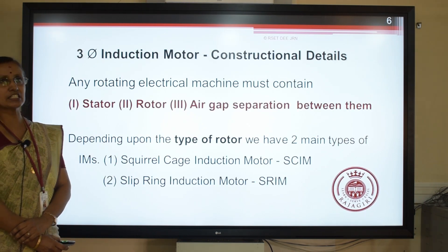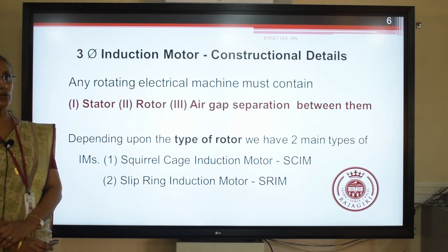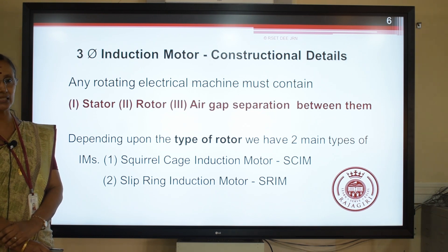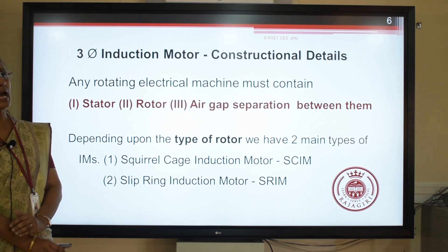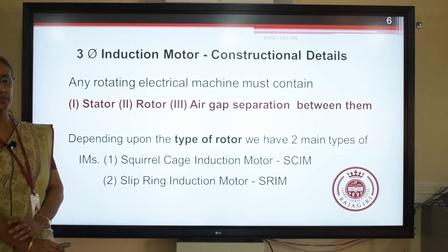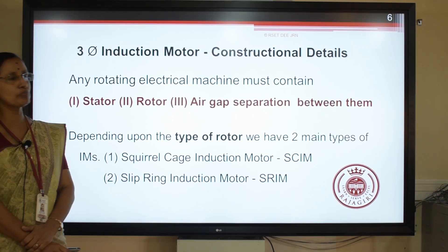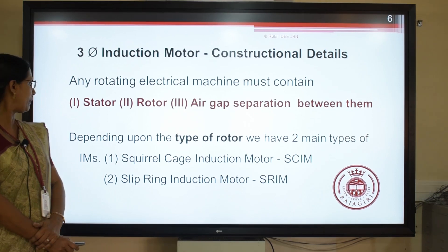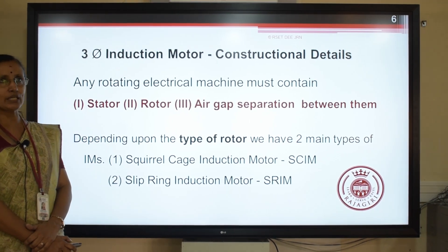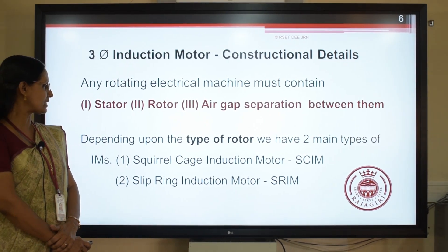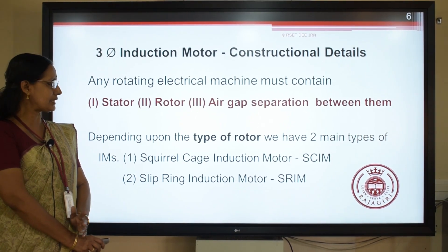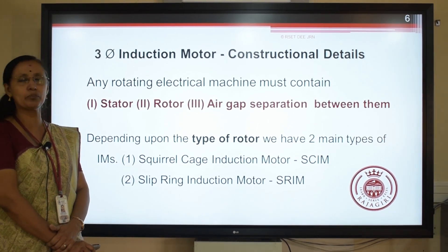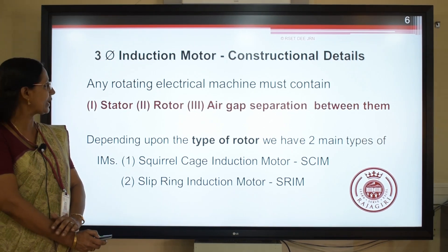Moving on to constructional details. Like any rotating machine, it needs a stator as well as a rotor, and between the stator and the rotor there is an air gap separation. The air gap has to be kept as minimal as possible — 1 mm to 3 mm. Depending upon the type of rotor, we have two types: one is a squirrel cage induction motor, commonly known as SCIM, and second is a slip ring induction motor, commonly known as SRIM.